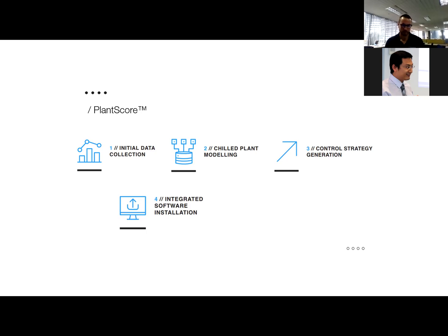That next step is then working with the incumbent BMS companies to implement the changes, so that's just writing control logic. We can output the model in a whole lot of different ways, so whether we're staging based on chiller loading or staging based on kilowatts of refrigeration output from the system, it doesn't make any difference for our model in terms of how it operates internally, but we can export those in ways that make implementation quite easy.